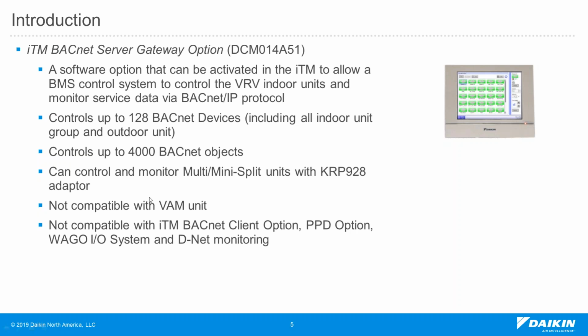It can also be used to control and monitor the multi-split and the mini-split units, but it cannot be used to control the energy recovery units, the VAM unit. And if you use the BACnet server gateway option, you cannot use the ITM BACnet client option, the PPD option, the Wago IO system, and the DNet monitoring anymore.